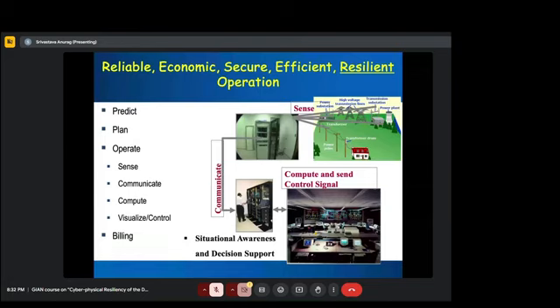Same thing you will do with the distribution PMU, which will be in the distribution system. You'll put the smart meter, which is a little bit slower to report. When we say slower and faster, it depends on multiple things, but two things are more important: the sampling size of that sensor, and the communication that can bring the data. The sampling for a smart meter can actually be really fast since it's local there, same as the CT and PT, which is an analog signal fed into PMUs.